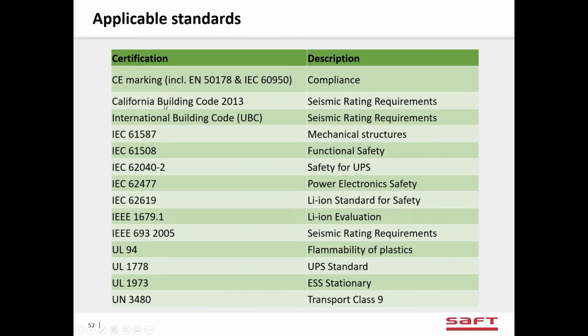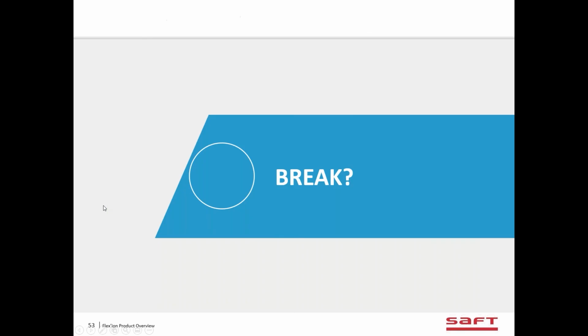These are a whole list of applicable standards that the Flexion system was designed to. In the US, the most important one is the second one from the bottom. UL 1973 is the UL listing for a stationary battery, a stationary lithium-ion battery. And we're fully compliant with UL 1973. There's a lot of other things. UN 3480 is the transportation rules, so that we have to certify that the battery can be shipped by air, sea, and plane or road. And it has to go through a transportation test. So depending on what codes and standards you need to meet, we probably can support that.